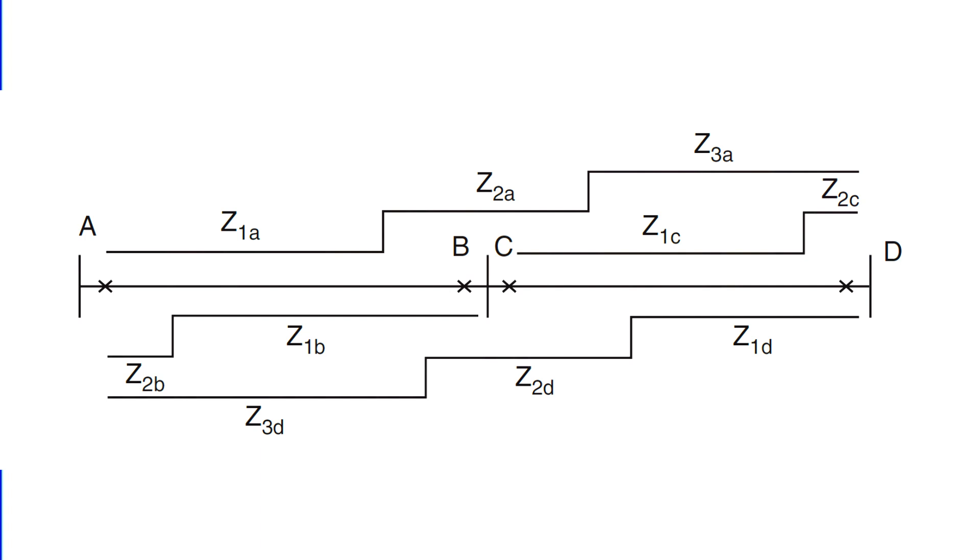Moving on to zone 2, or Z2A. This zone steps in to cover not only the remaining 20% of the line AB, but also extends to 20% of the adjoining line. As we delve deeper into the specifics of Z2A, it's crucial to understand its strategic importance in the overall network protection strategy.